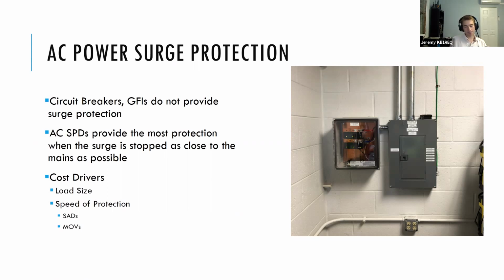So that's more expensive, but again, provides you the best level of protection. When it comes to cost with these devices, no matter where they're located, the speed of the protection is also another cost driver. For more sensitive or more expensive electronics, where a shorter clamping time is needed, you're going to pay more, because you're going to essentially have two devices in there that are doing that shunting.